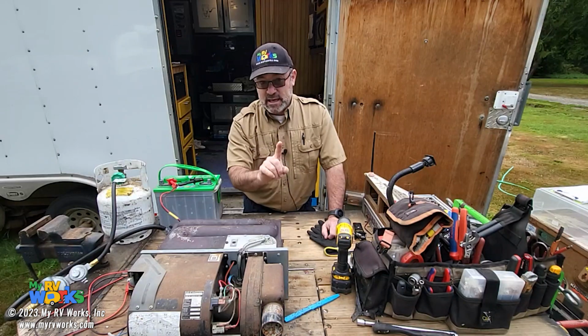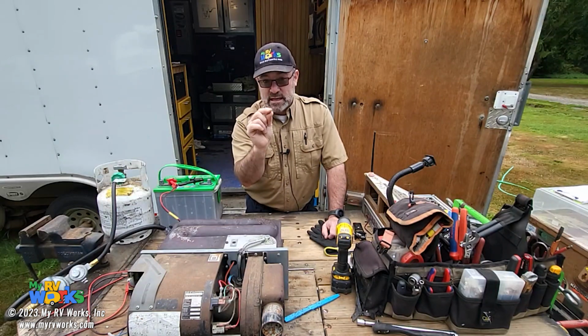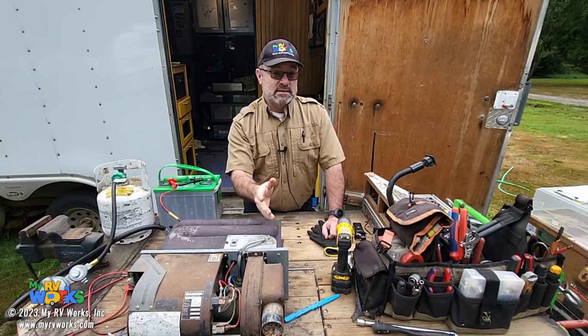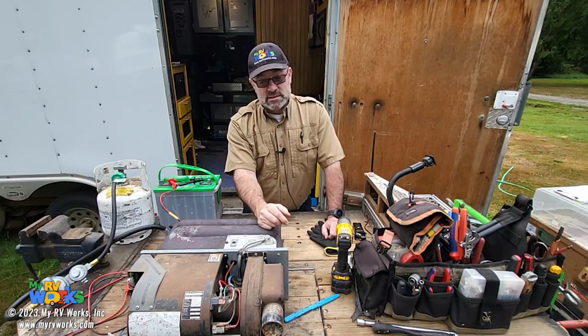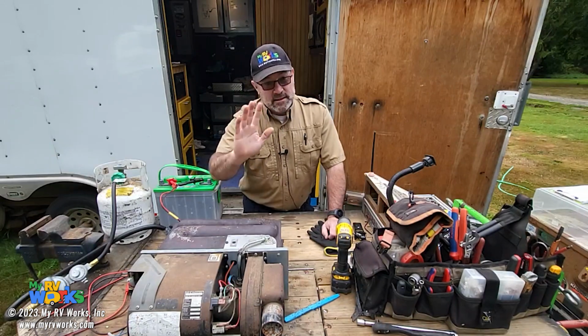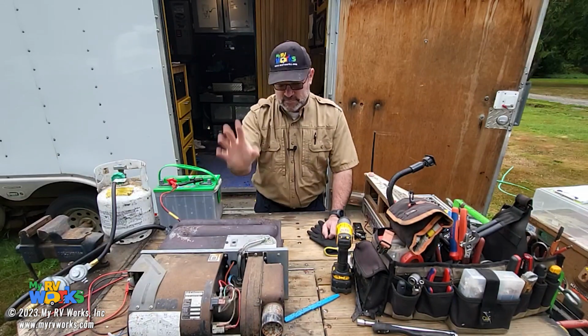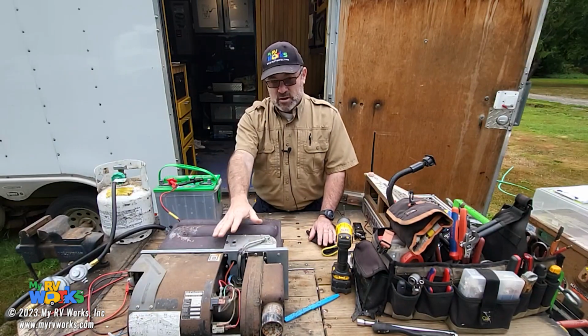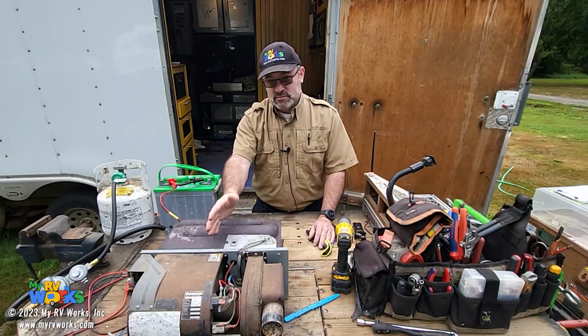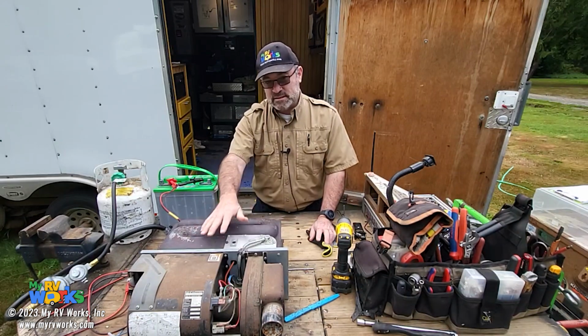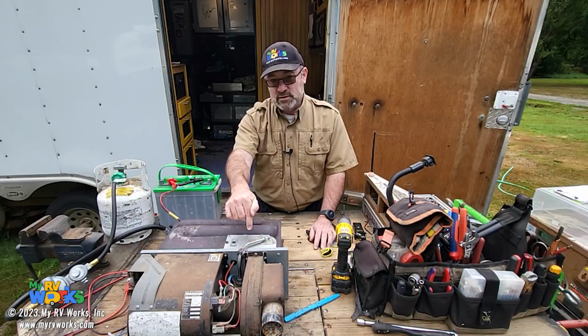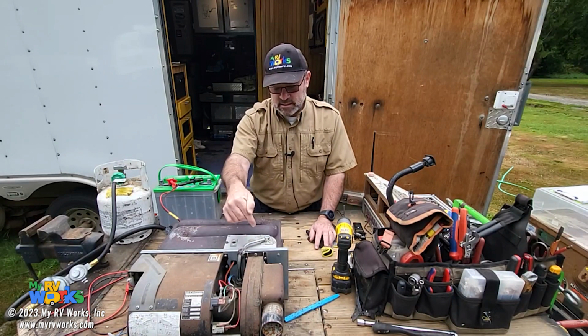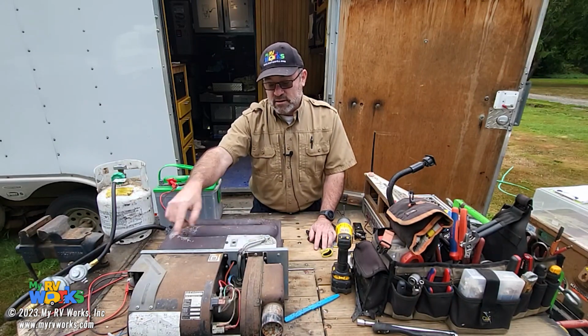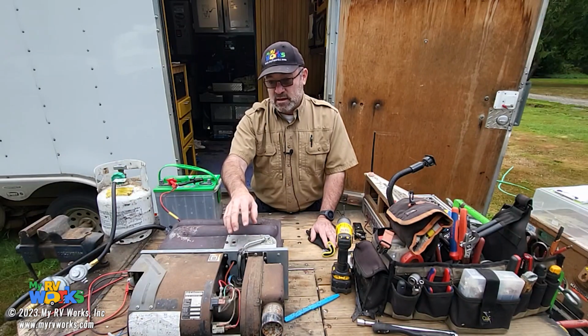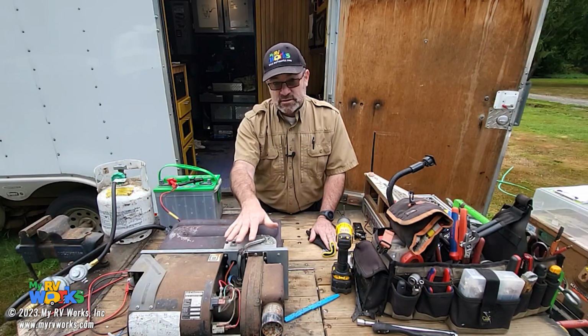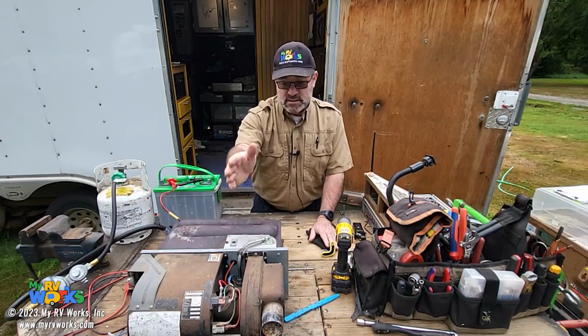However, at the end of the day, this furnace needs 2 wires to make contact. It needs 12 volts coming back to it. Even that can't be a blanket statement, because on some of your Suburban thermostats you only have 1 wire coming back. We'll save that for another time, but let me stay on point. We were talking about the furnace having an intermittent issue: extinguishing its flame, starting its flame, extinguishing its flame, starting its flame. I said that one thing could be the electrode wire, the ceramic in the electrode gap, or the control board itself. All of those would be an indication of the control board extinguishing the flame because it shut off the gas valve.